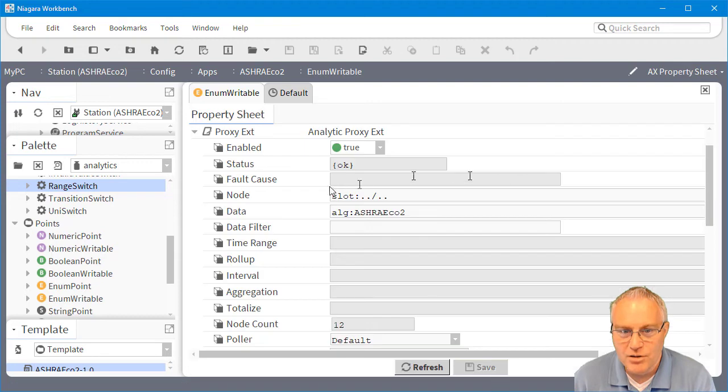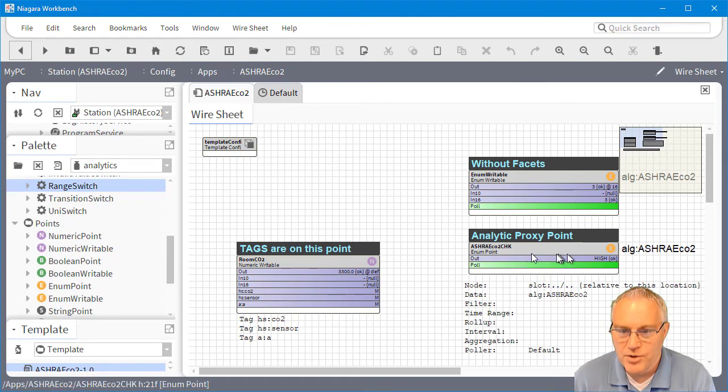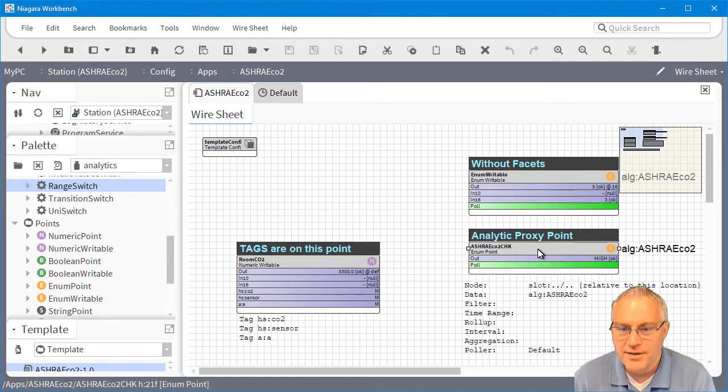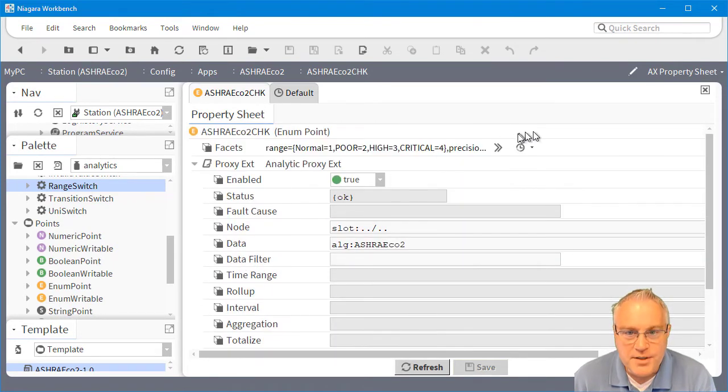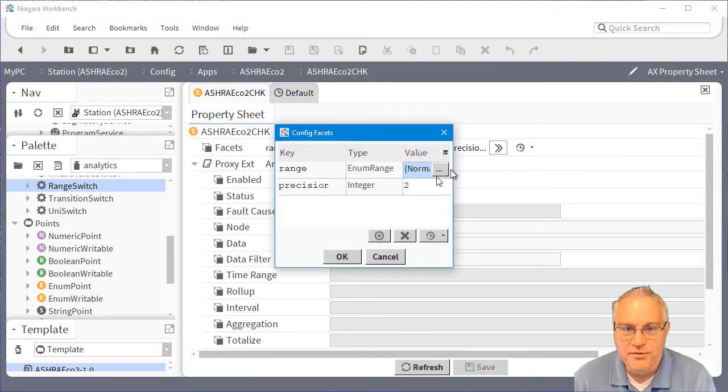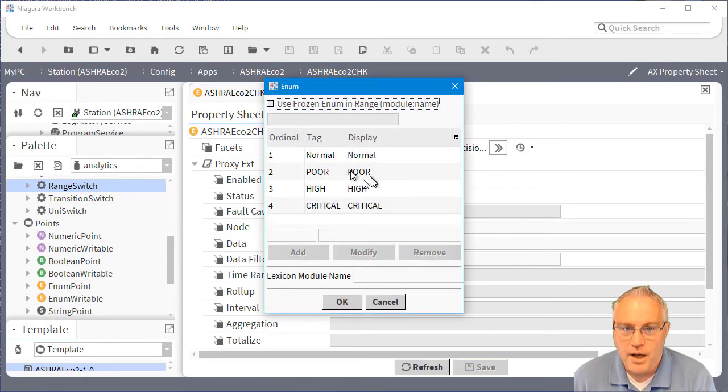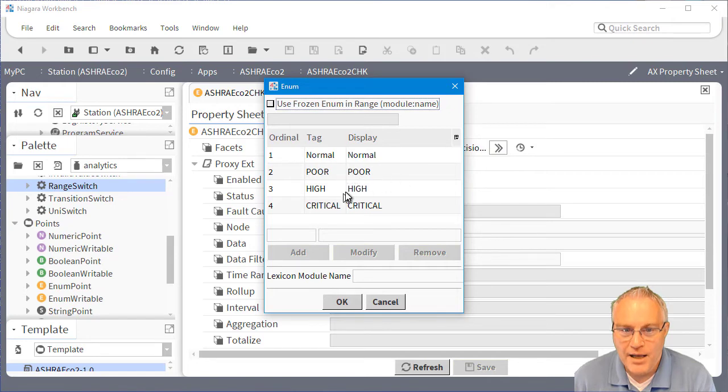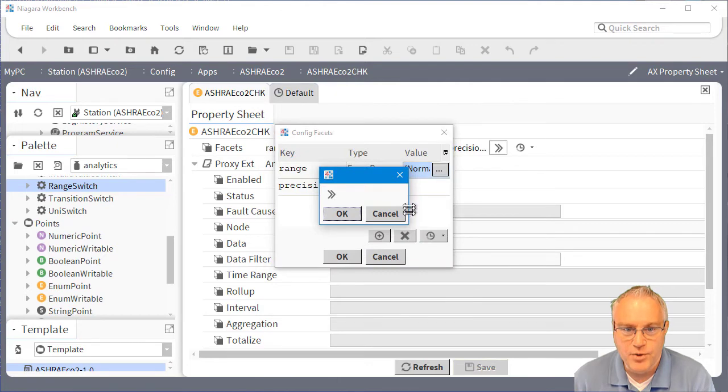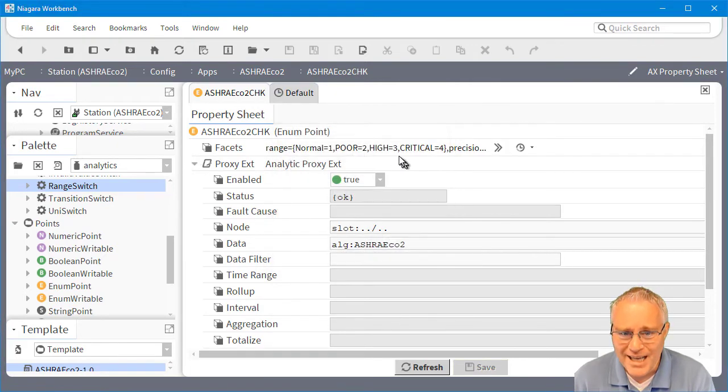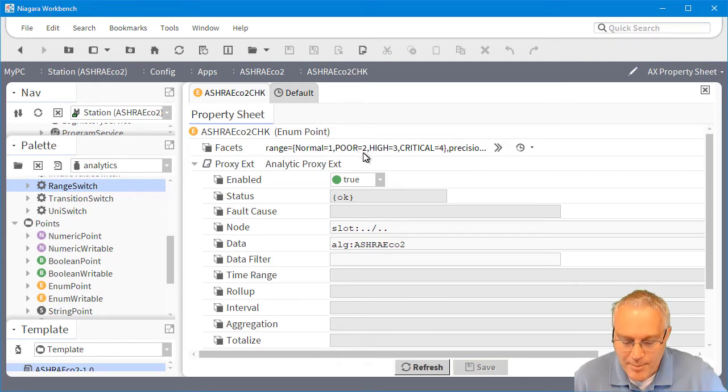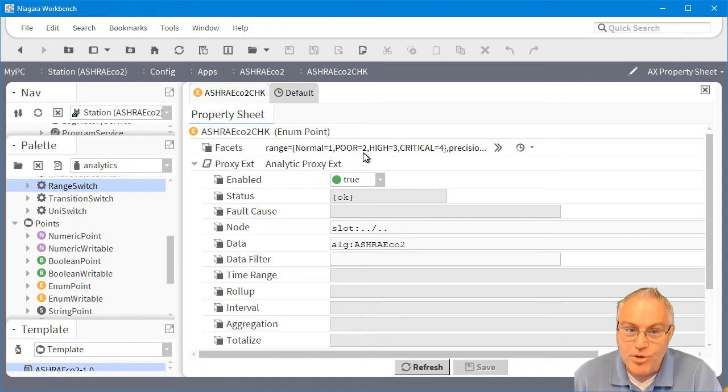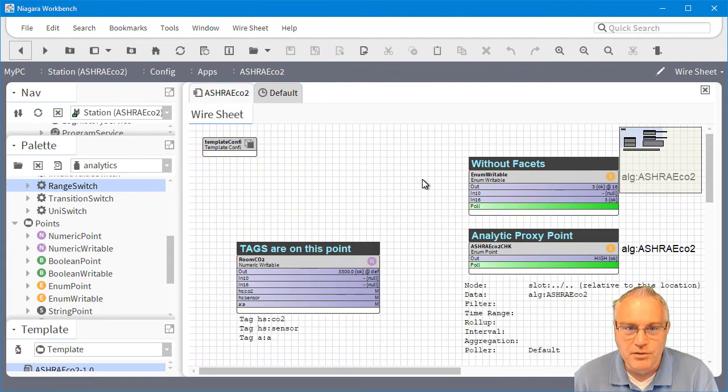This one is just showing you the value coming through, and this is showing you the actual string that I set up for the facets. If you come down here and look at this, I have a series of facets that give me what I want to have. I have normal, poor, high, and critical based on those numbers that I pass through. I did it this way so I could trap that. Instead of doing a number, I didn't want to trap from zero to one thousand. This just allows me to do the animation a little easier in the PX page.